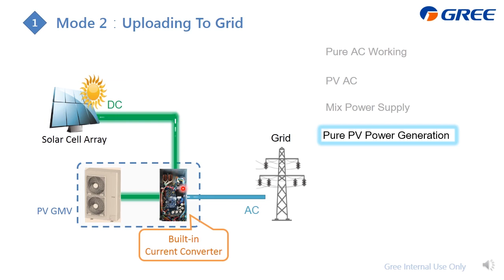Mode 2 is uploading to the grid, and this requires the local policy to allow it — if it allows, you can upload to the grid power supply to earn some money. For this mode, first is pure PV power generation: if the PV-GMV is not working, the PV panels still generate power, which you can upload to the grid to earn money. The next is the balance mode, which means if it generates a lot, it can power the PV-GMV and also upload the surplus. This is the perfect case. For these two, once set, there's no need to change anything.